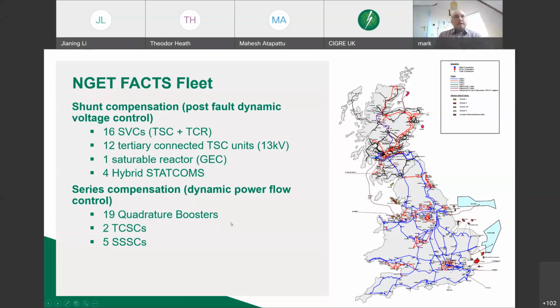It's typically divided into two areas. What's called shunt compensation, connected to ground, primarily used to support the network to manage dynamic voltage control, so that during faults we can hold the volts up or pull them down depending on the oscillation to try to maintain the system in a stable nature so it can recover safely from a fault. We have a variety of technologies from the traditional static VAR compensator up to the more recent StatCom designs, which I'll talk through in a few slides' time.